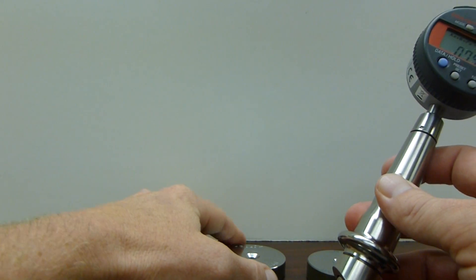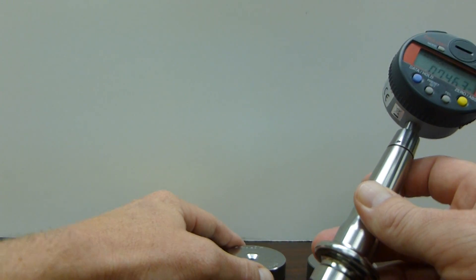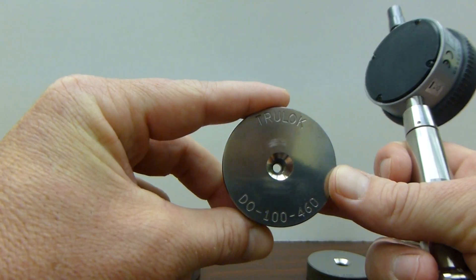Our gauge comes equipped with a setting block at the nominal value to calibrate this gauge. In this case, it is a DO100-460.